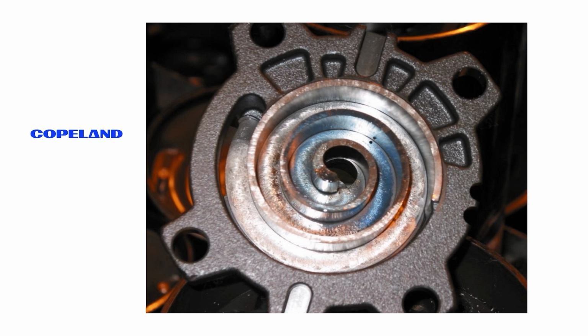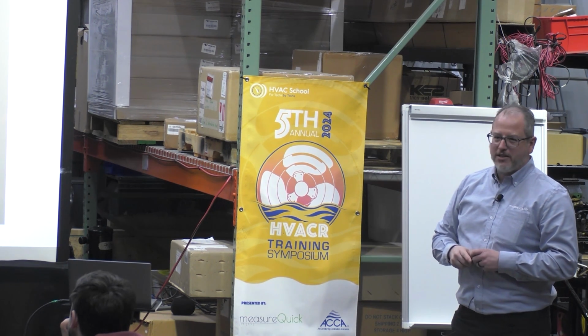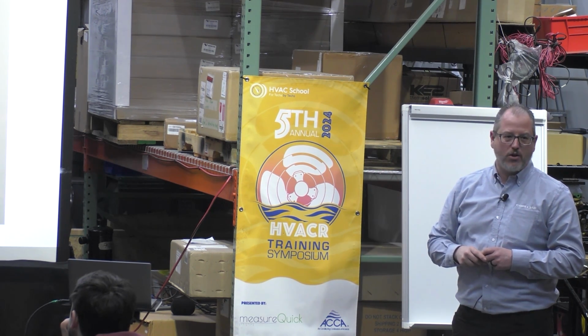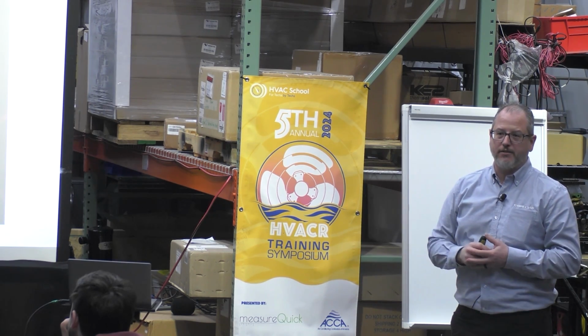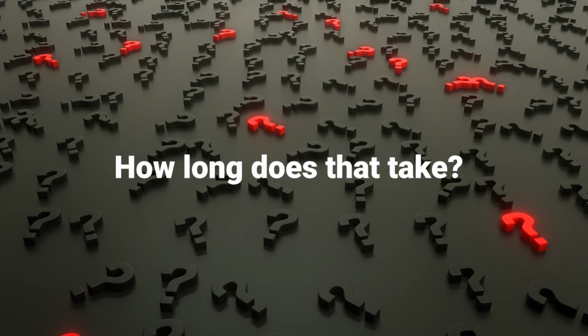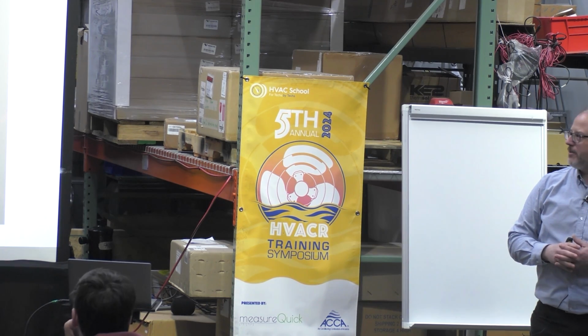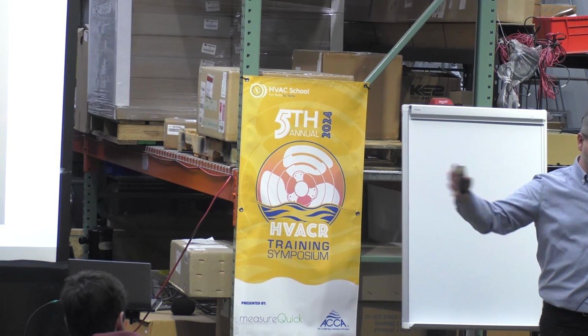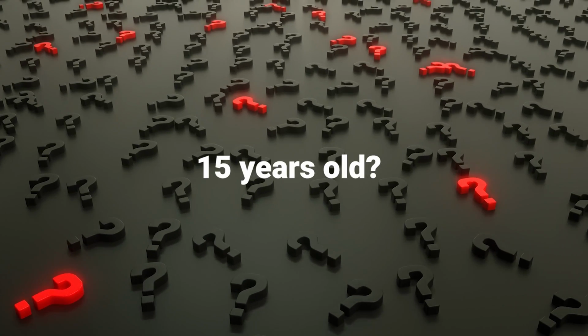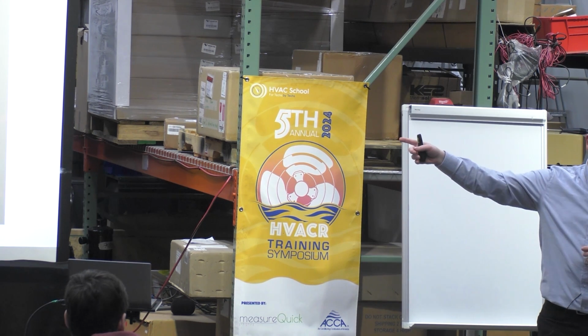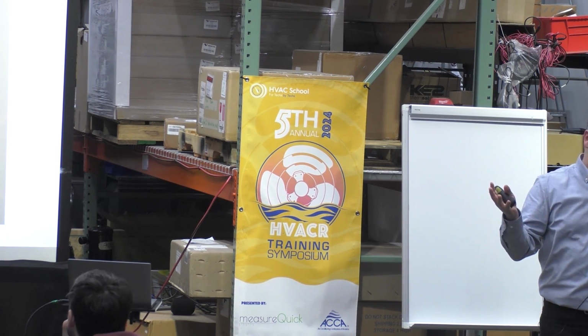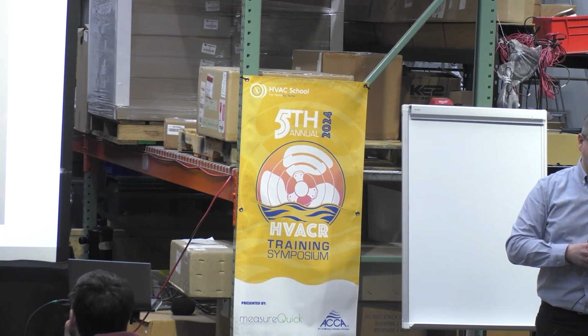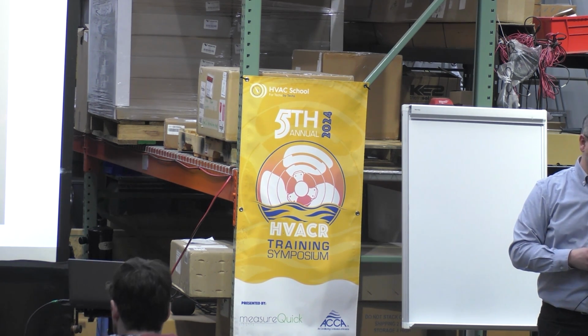Here's a scroll set with bluing in there. Now this is not something you can say, hey Copeland, I want one of those cool blue scroll sets. This has to be earned, right? That just doesn't happen. So if we take apart a compressor and it looks like that, we know that it has been overheated, right? How long does that take? Depends on temperature. Generally, it depends on the temperature, but a lot of times with overheating, it happens over a long period of time. So 15 years old, not necessarily. I've seen it 6 months old. But it might be a system that runs constantly. But if it's constantly overheated for 6 months, it'll do that.